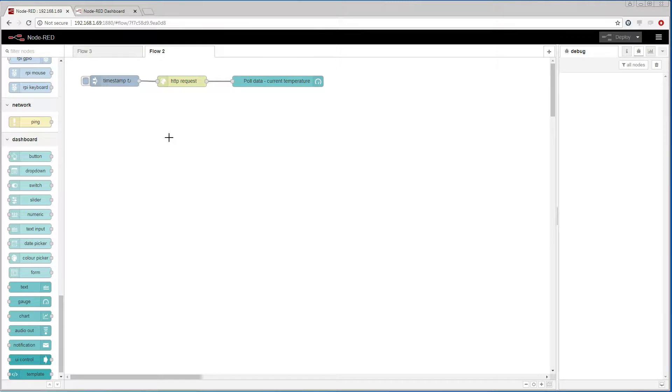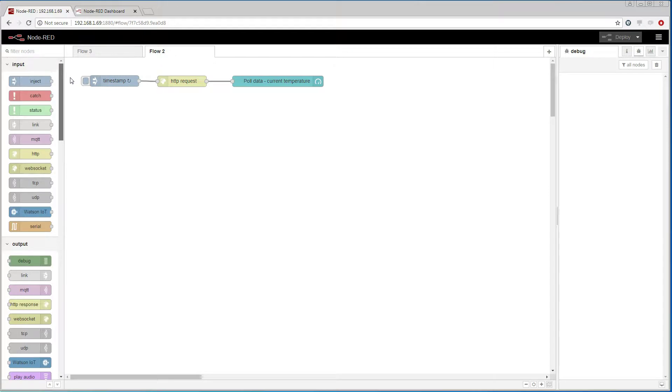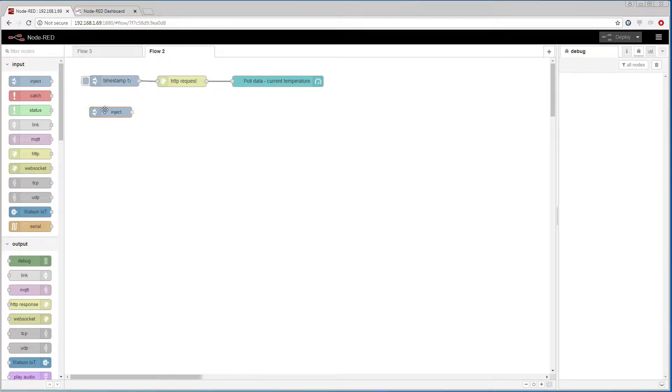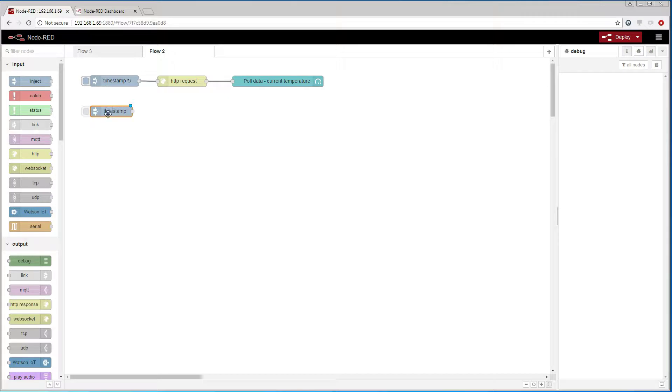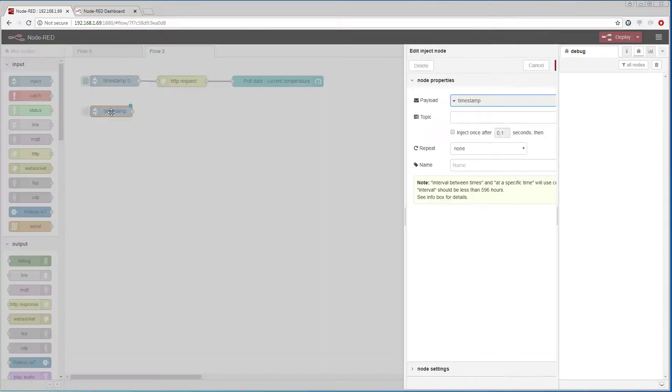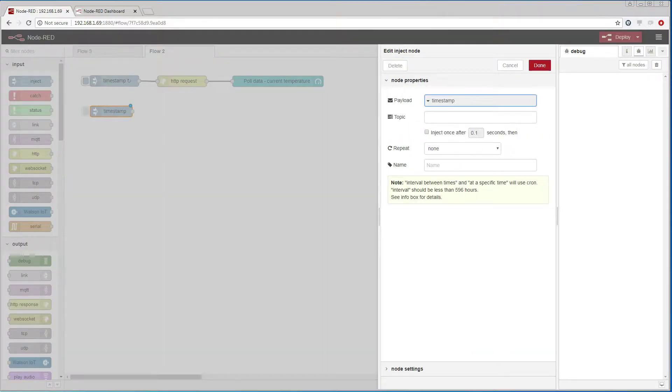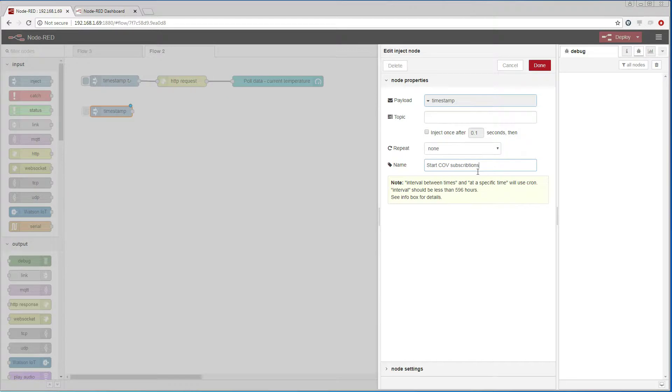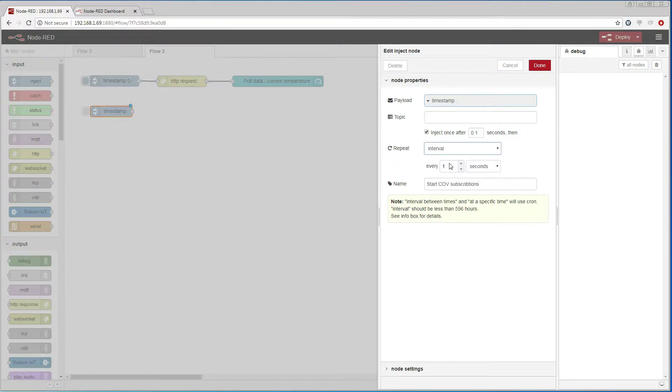Now let us set up a COV subscription. Our subscription has a lifetime and in my case it will be 60 seconds. So I add an inject node that will be responsible for creating a COV subscription and it will create a new one every 65 seconds when a previous subscription expires.